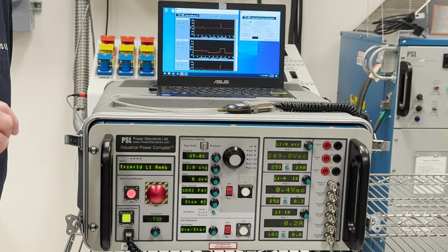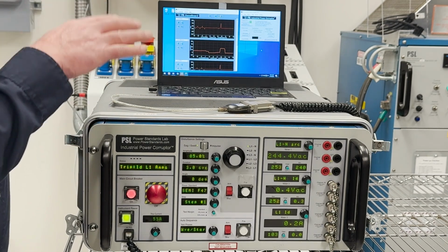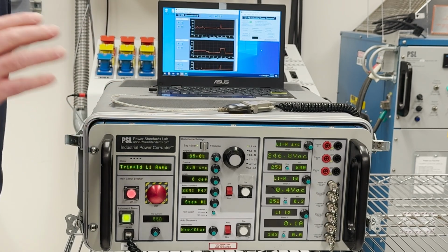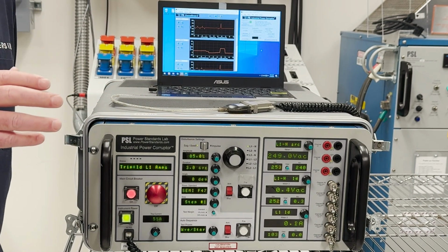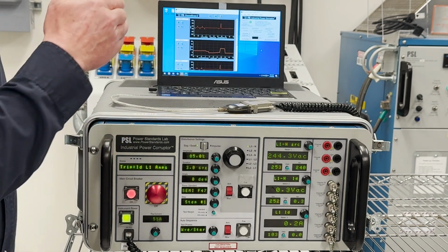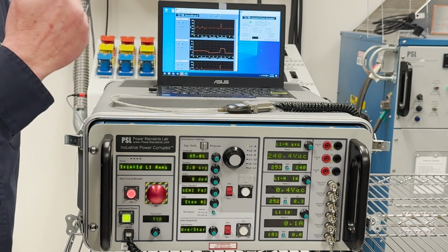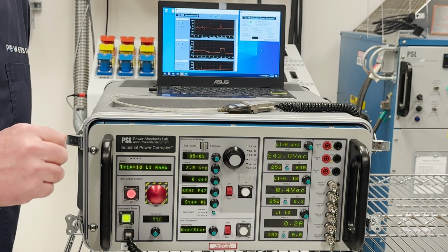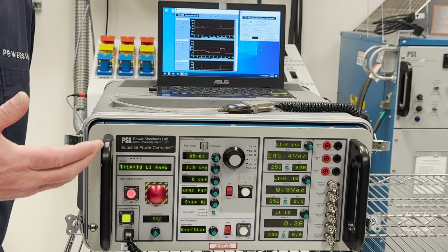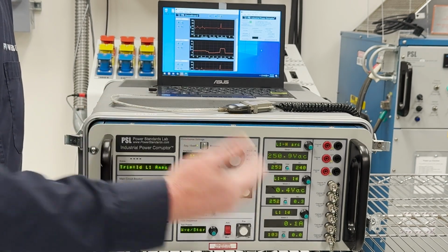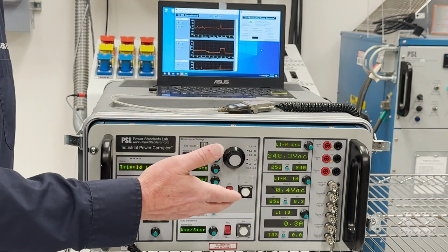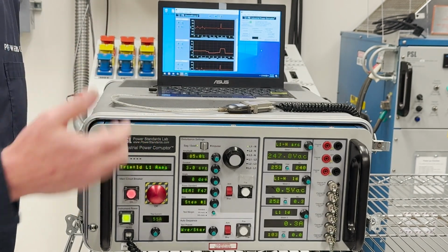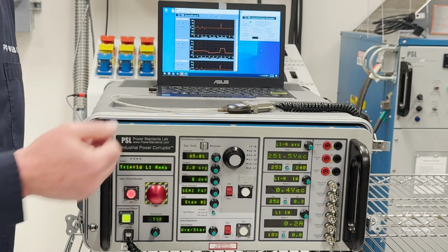And this should be a word of caution to you. The IPC is set up for a 200 amp peak in terms of inrush current, right? In terms of current. If you exceed those limits, you risk damaging the relays in the IPC, and then of course the IPC needs to go back to be refurbished and repaired. So don't imagine that your nominal load is an indication of what you may see as inrush, especially if you have capacitive or regenerative loads in your unit under test.